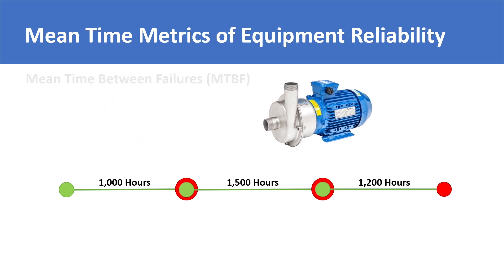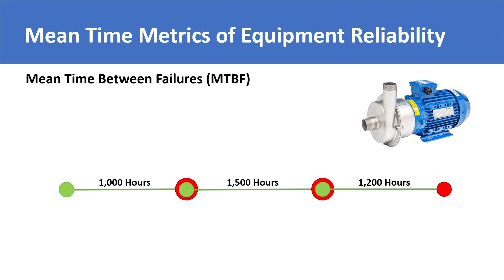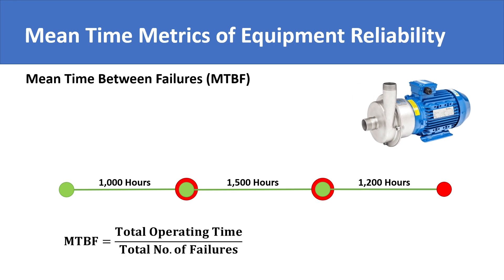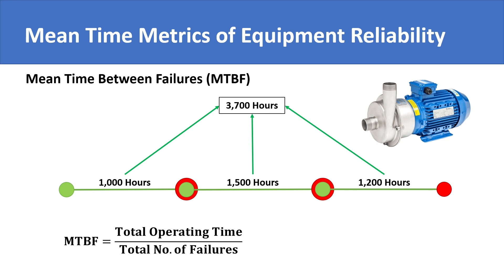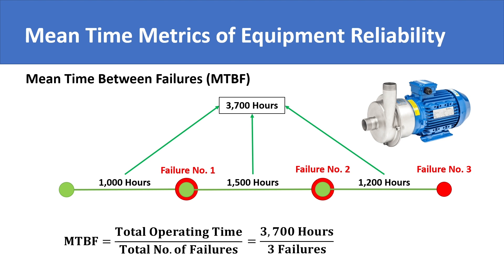The mean time between failures is simply the total operating time divided by the total number of failures. Our total operating time sums up to 3,700 hours and we have a total of three failures. Plugging in the values gives us a mean time between failures of 1,233 hours.